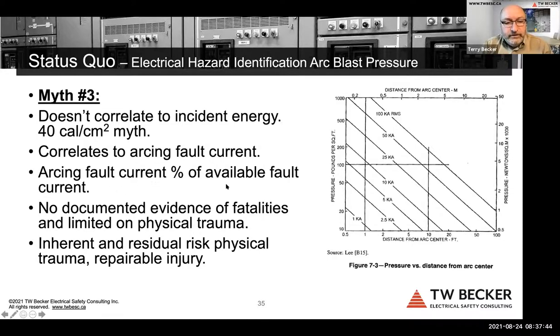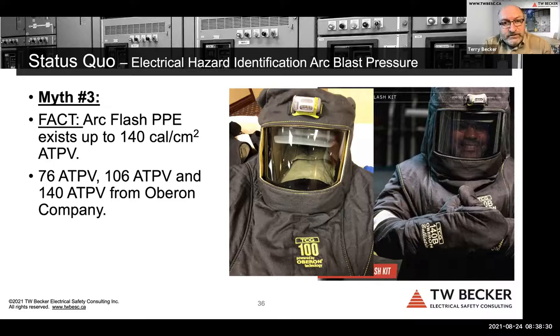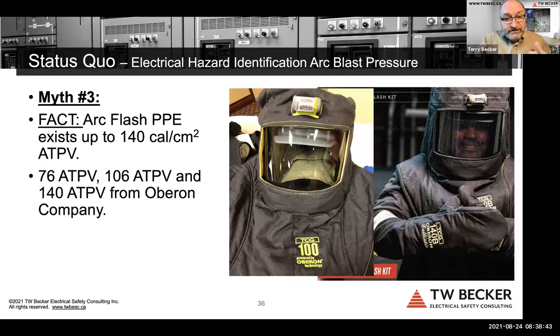There are no documented fatalities due to arc blast pressure. Residual risk related to blast should be assessed as physical trauma and repairable injury. As for Myth 3's claim that no PPE exists above 40 cal — that is false. PPE exists up to 140 cal/cm². Oberon Company's Arc 100 true-color gray arc flash suit is rated at 106 cal/cm², and their 140 cal/cm² flash suit has been available for over 15 years. This PPE performs the same as lower-rated PPE in terms of 50% probability of onset of a second degree burn injury.